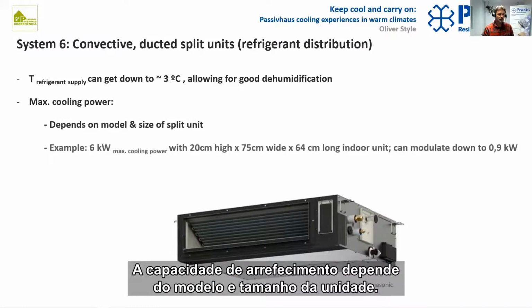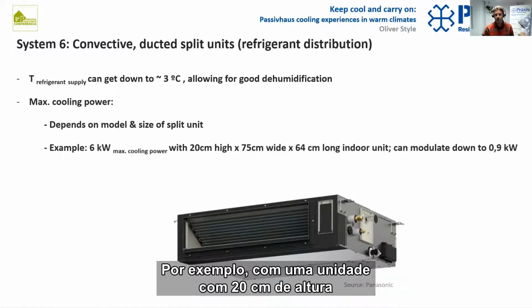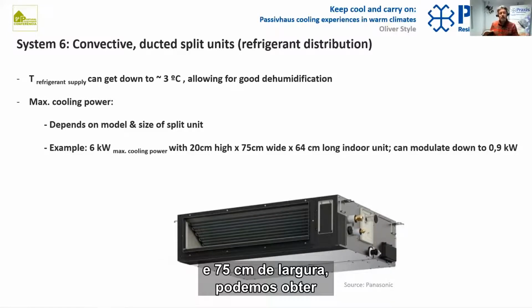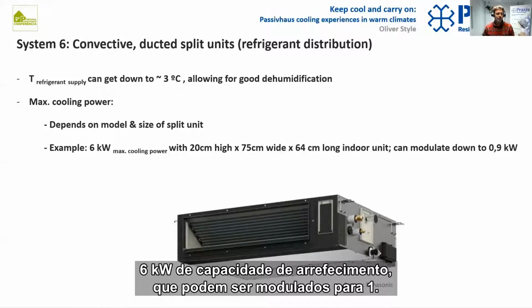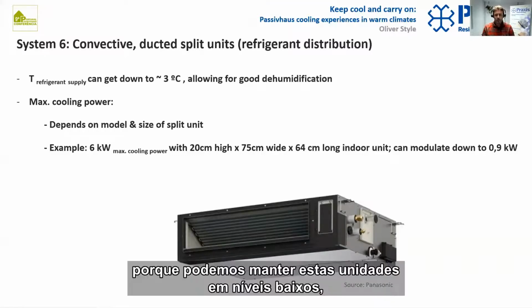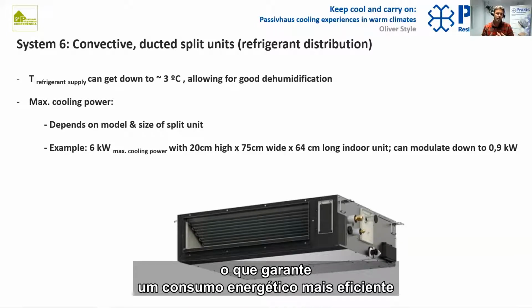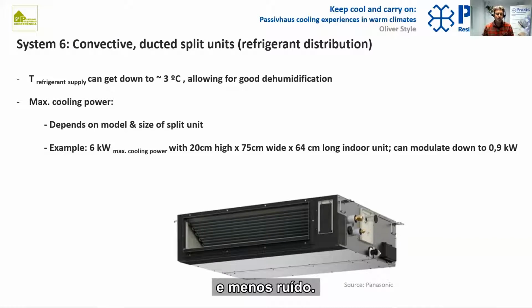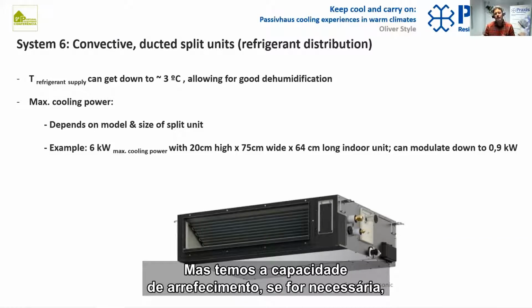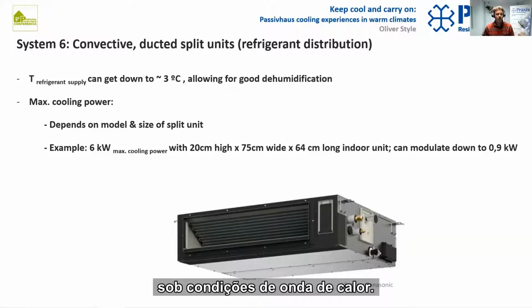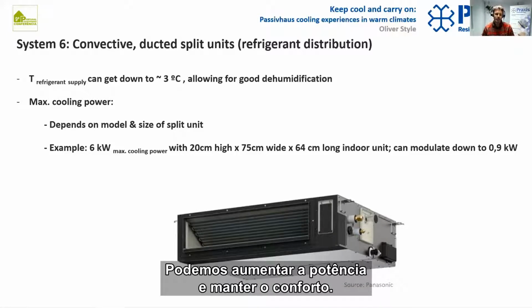Maximum cooling power depends on the model and size of the split unit, but for example, with a 20 centimeter high, 75 centimeter wide ducted split unit, we can get 6 kilowatts of cooling power, and that can modulate down to 1. So in a passive house, that's interesting because it means you can run these kind of units at low flow rates. That means that it's more comfortable, better, more efficient, less energy consumption, and less noise. But then you have that cooling power if you need it under heat wave conditions. You can crank it up and still maintain comfort.